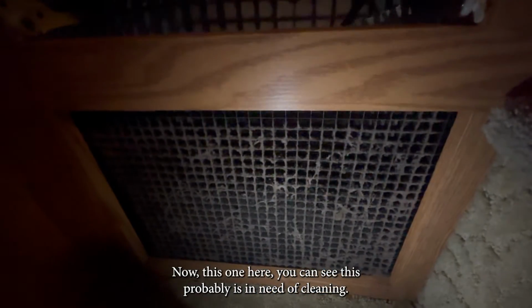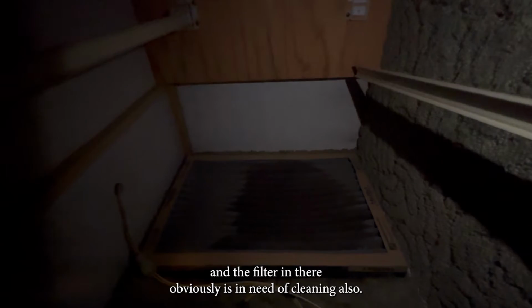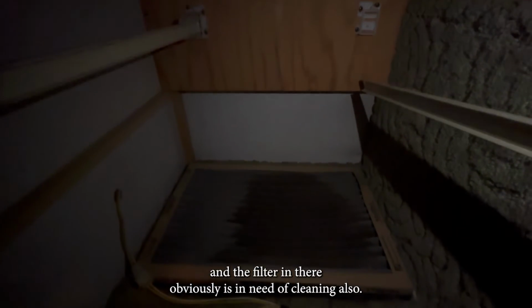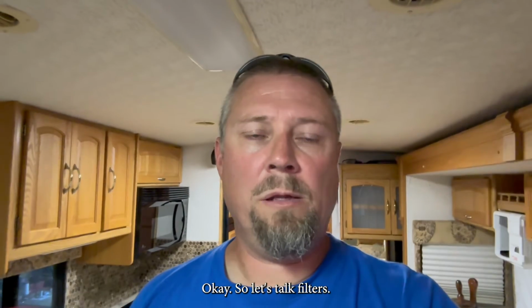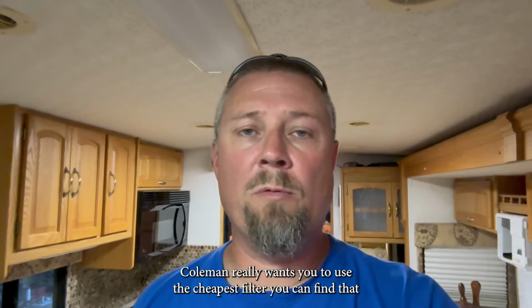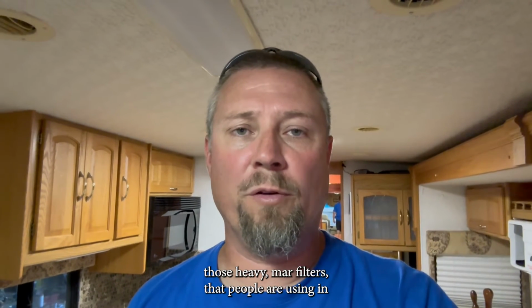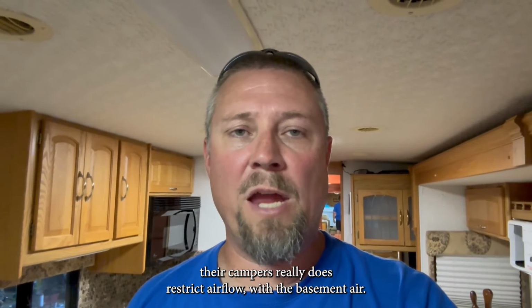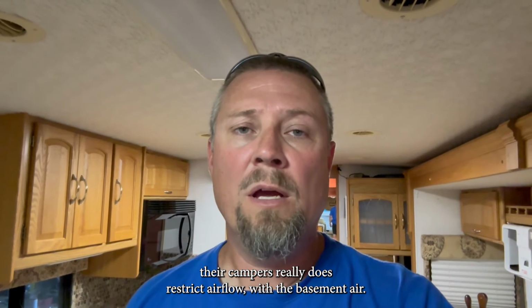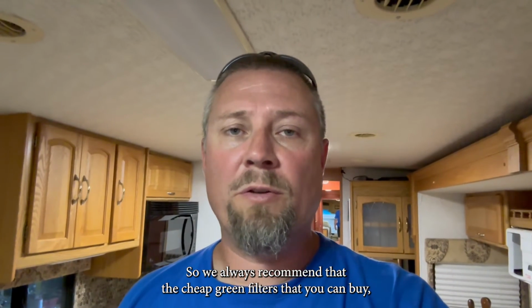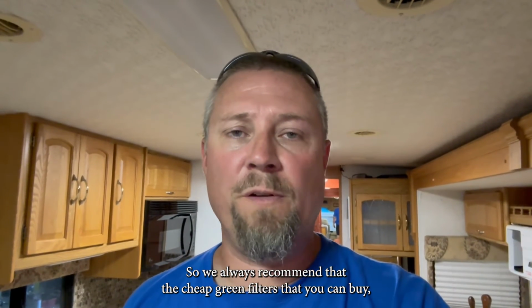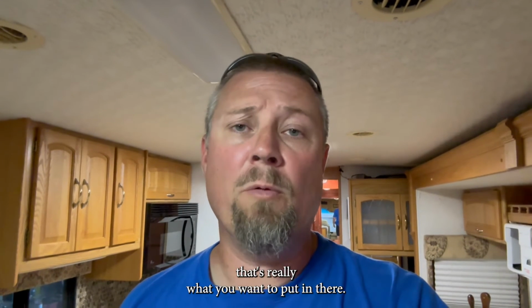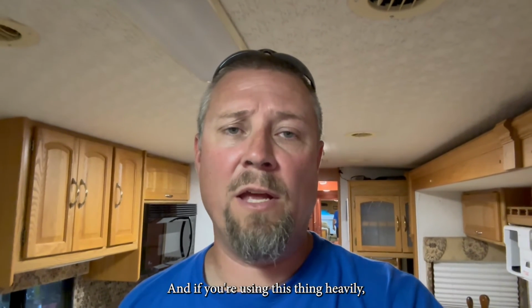Now, this one here, you can see this probably is in need of cleaning, and the filter in there obviously is in need of cleaning also. Okay, so let's talk filters. Coleman really wants you to use the cheapest filter you can find. Those heavy MERV filters that people are using in their campers really do restrict the airflow with the basement air. So we always recommend the cheap green filters that you can buy. That's really what you want to put in there. And if you're using this thing heavily, you really need to be changing that filter once a month.